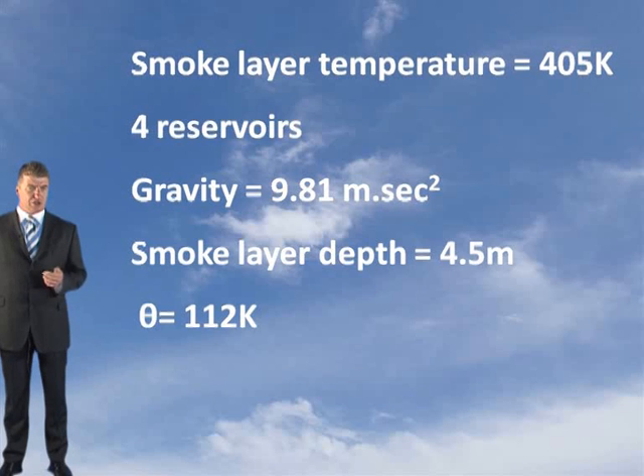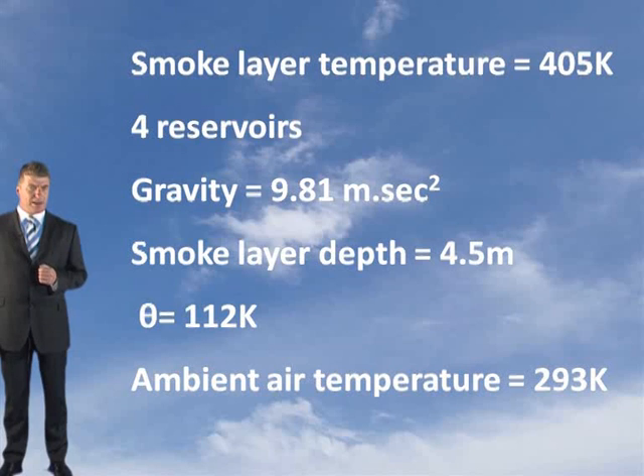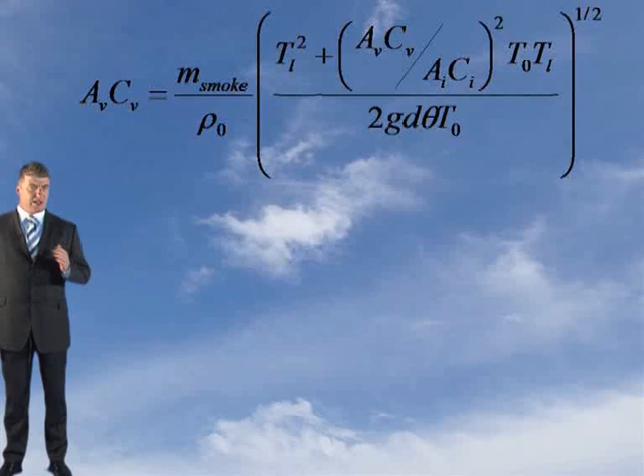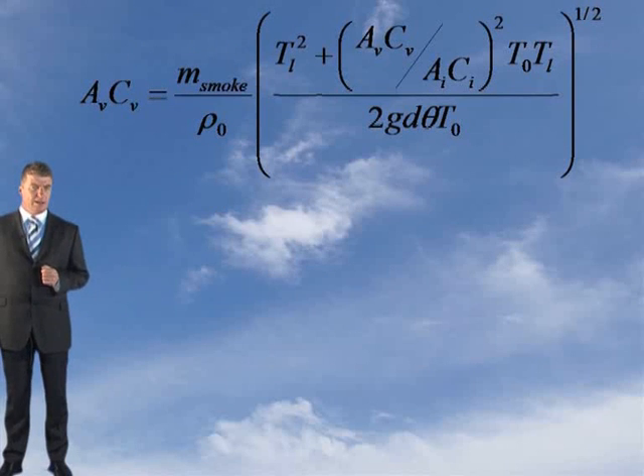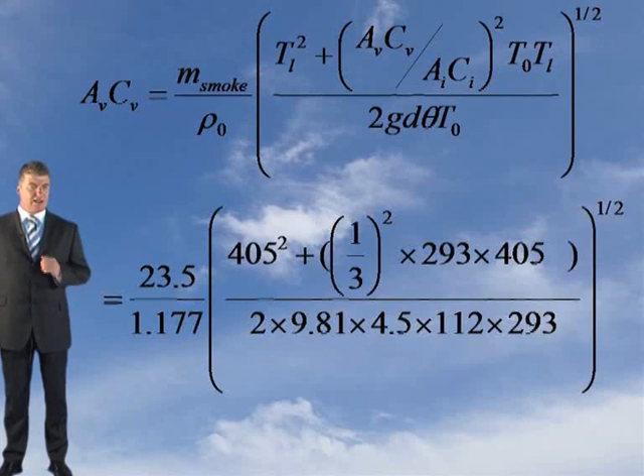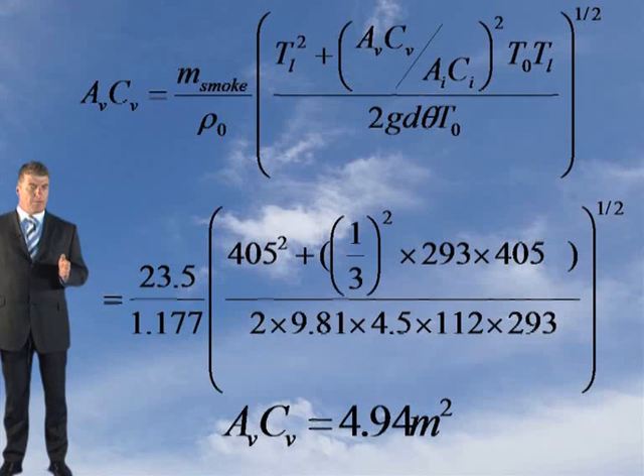Your temperature increase, the theta value, is 112 degrees Kelvin. The ambient air temperature can be taken as 293 degrees. Putting those figures into this formula, as you can see here, you should get an AVCV factor of 4.94 square meters.